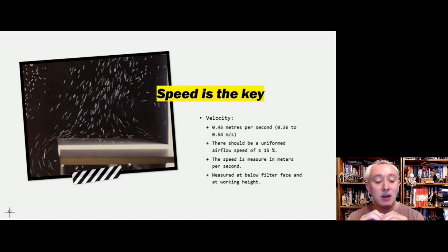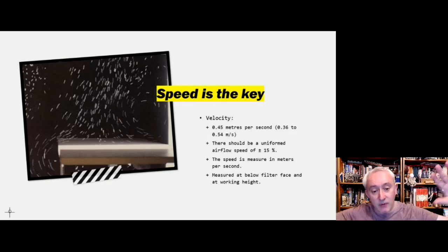So we maintain this by having a relatively fast airflow and air velocity of target 0.45 meters per second, plus or minus 20%, which in reality is 0.36 to 0.54. And also we want to make sure that the airspeed across a HEPA filter is uniform, and by uniform that's within plus or minus 15% of each value.